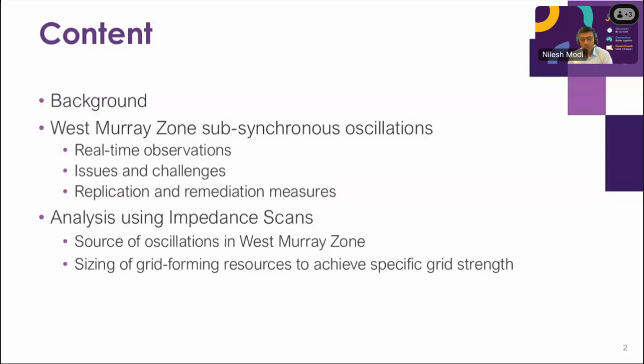Then I'll hand it over to Shahil, who will go through the impedance scan and how this tool can be used to identify the root cause of oscillation. At the same time, how this tool can be used to size the grid forming resources to achieve a specific grid strength and to eliminate these oscillations.